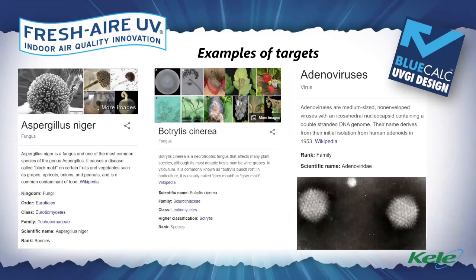As you recall, I pointed out Aspergillus niger as the hardest of all bacterial spores to inactivate using UV light, requiring 330,000 microwatts. So we like to use that as our de facto benchmark pathogen for coil irradiation, but we also have many other fungi and viruses. Adenovirus is about 7 times more resistant to UV than coronavirus, so we like using that as our benchmark as well. But if you, your customer, or you as a facility owner have a specific target in mind, we could base our calculations on that target.